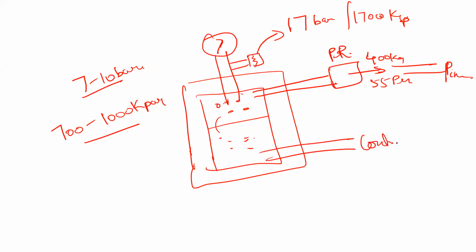When you have an excessive demand for oxygen, like in the current situation, the control valve opens directly, draws away the liquid, and it is superheated by copper coils, and the heat for the superheat comes from the external atmosphere. Then it goes to the pressure regulator, then to the pipeline. So this is the basic working principle of the liquid oxygen tank.